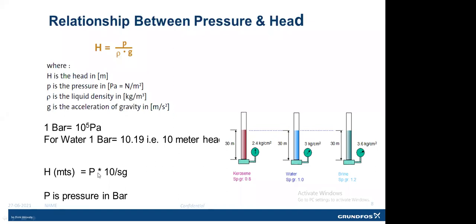For water, we can straight away say if differential pressure is 2 bar, it's 20 meters of water column differential pressure, or 20 meters of head available, or the pump is operating at 20 meters of head. If it is another liquid, we need to take specific gravity into account as well to calculate, or to check, the exact head at which the pump is operating.